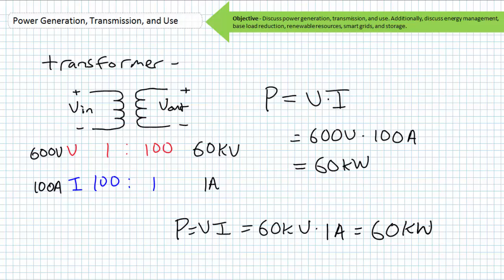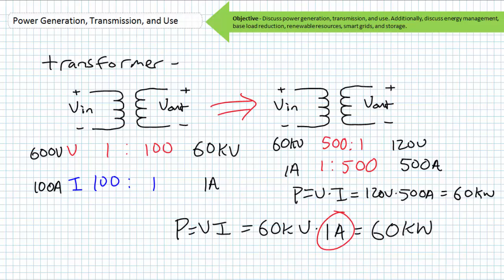At the point of consumption, another transformer steps down this high voltage to a safer, more usable level. If 60 kilovolts and 1 amp of current enters a 500-to-1 step-down transformer, the voltage is decreased 500 times to 120 volts, and the current is increased 500 times to 500 amps. Again neglecting complicating details and inefficiencies, 120 volts times 500 amps delivers 60 kilowatts of power.